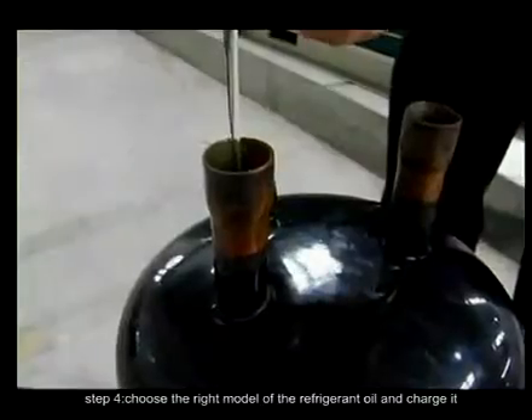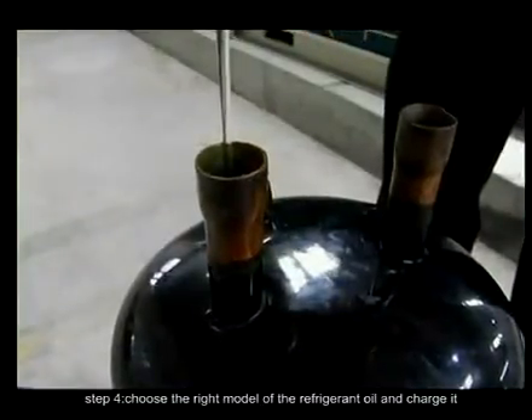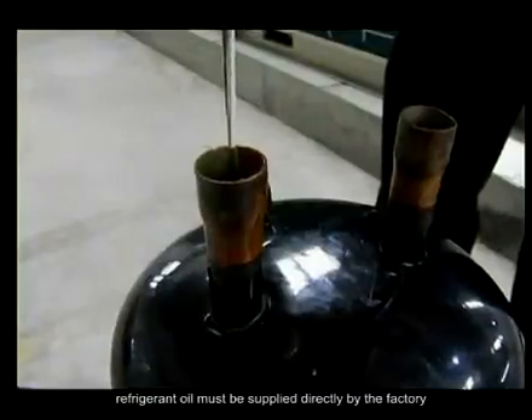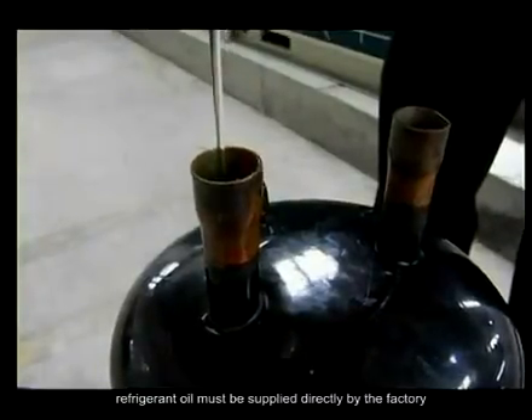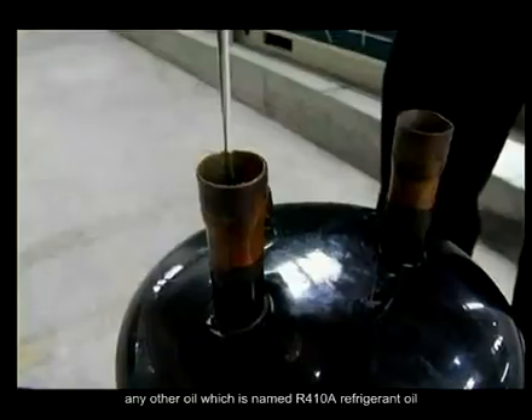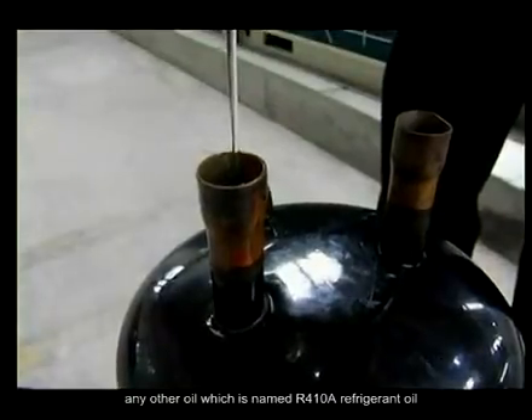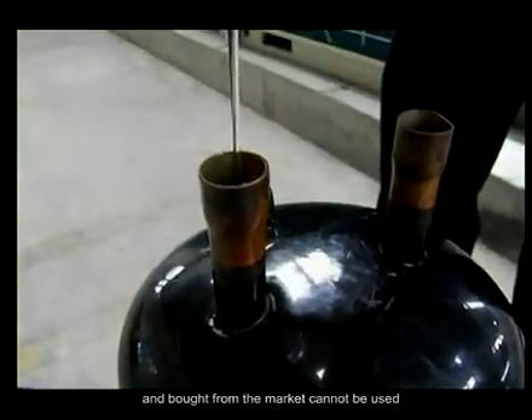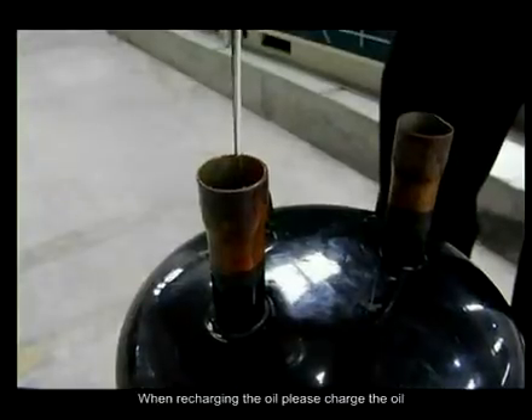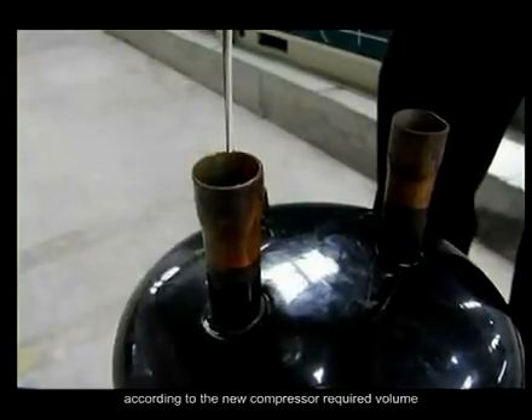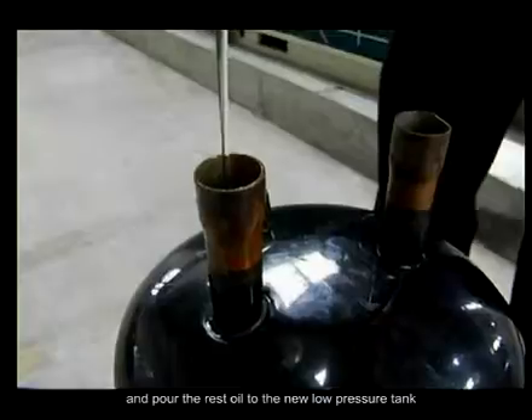Step 4. Choose the right model of refrigerant oil and charge it. Refrigerant oil must be supplied directly by the factory. Any other oil named R410A refrigerant oil bought from the market cannot be used. When recharging the oil, charge it according to the volume required by the new compressor and pour the remaining oil into the new low pressure tank.